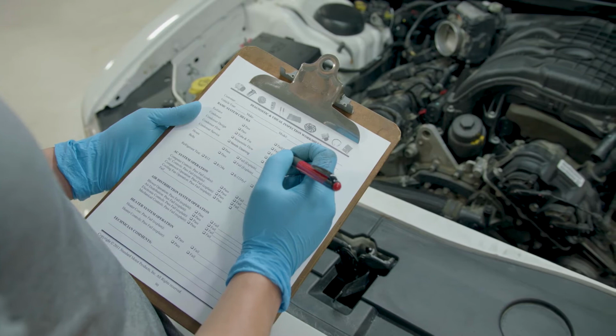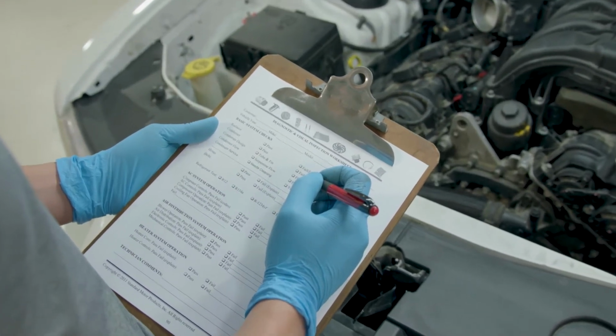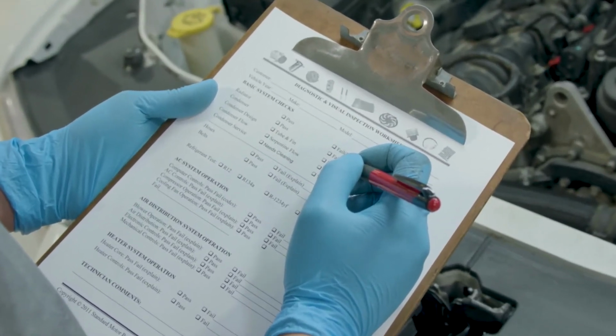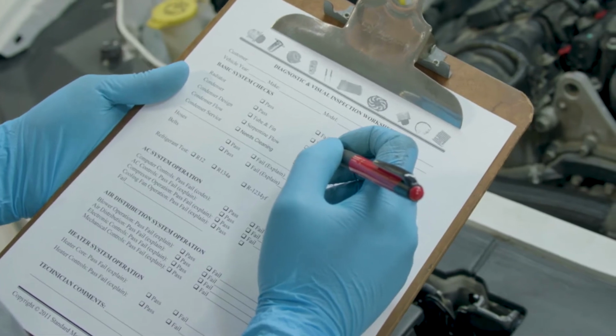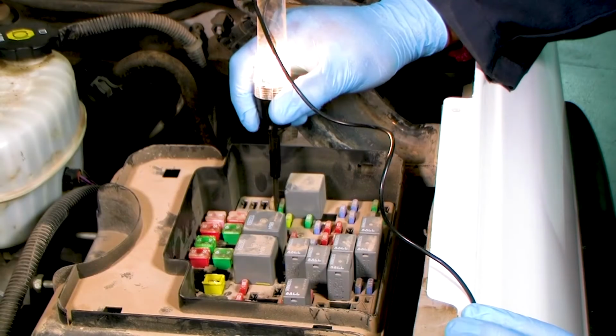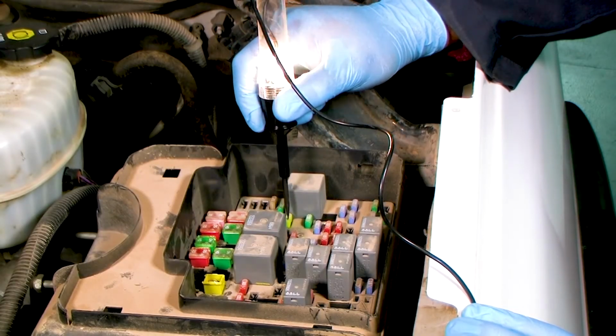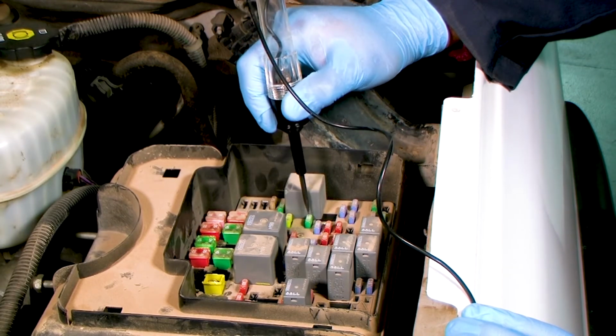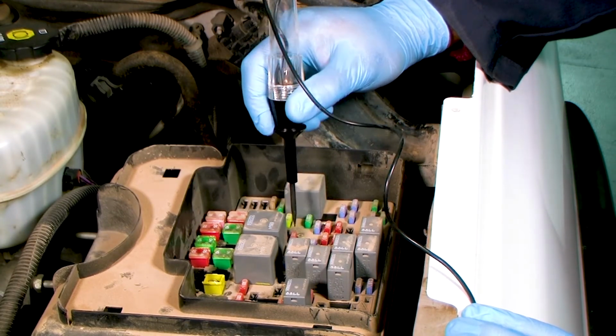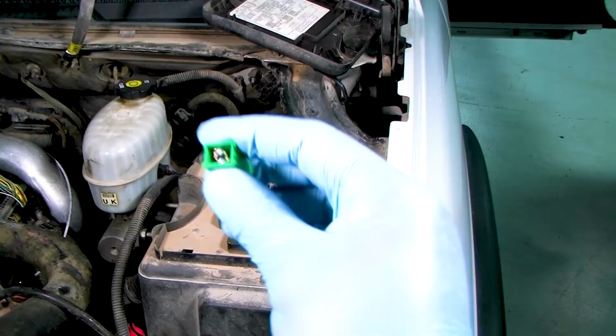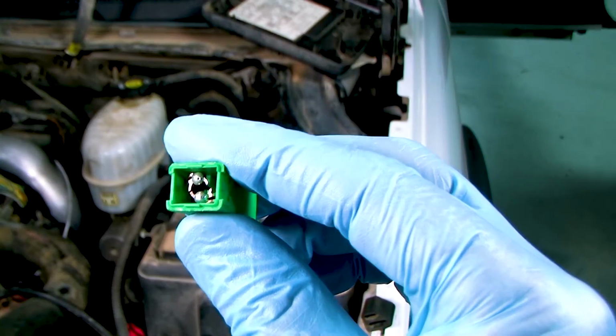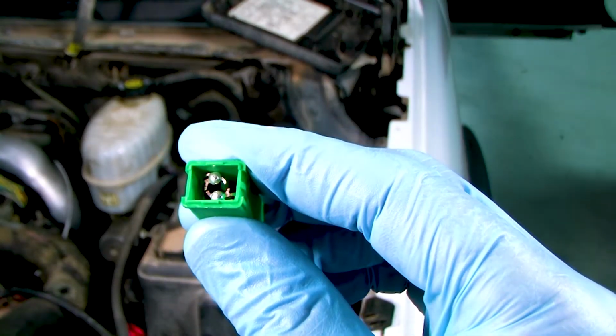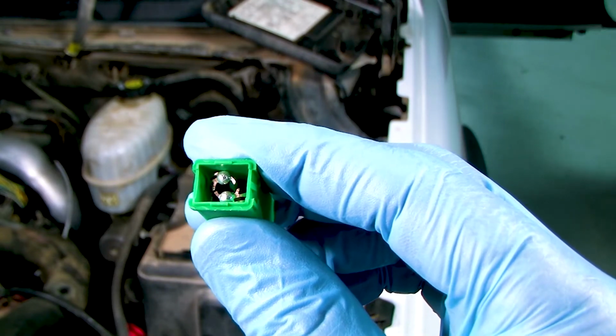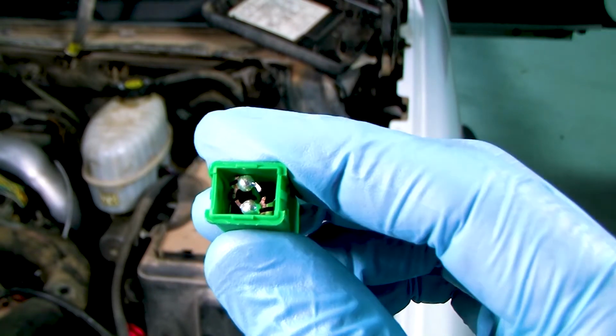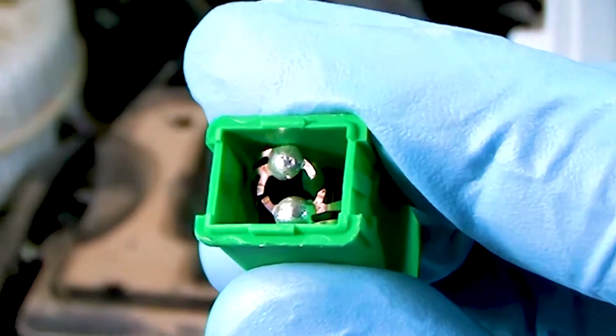Using customer interview and inspection worksheets can often help you gather critical additional clues that can speed your diagnostic path. Checking fuses at the outset is usually a lot faster than diagnosing the circuit only to find a blown fuse later. Also, finding a blown fuse early can get you pointed in the right diagnostic direction quickly. For example, a blower motor may be drawing too much current, causing the fuse to blow.